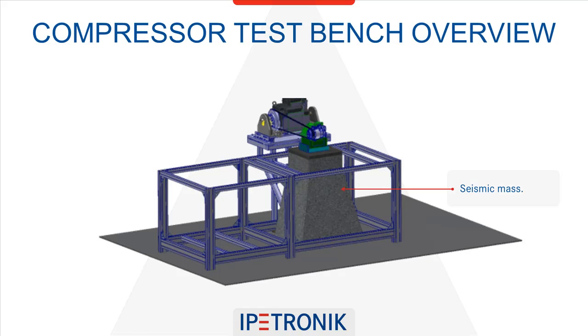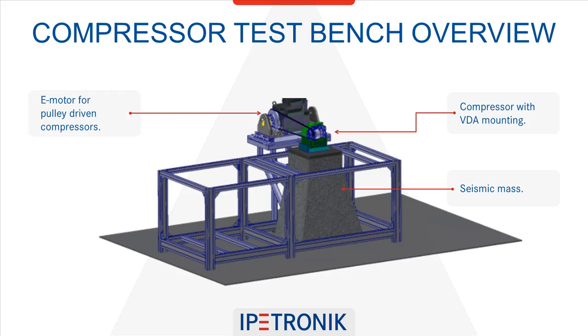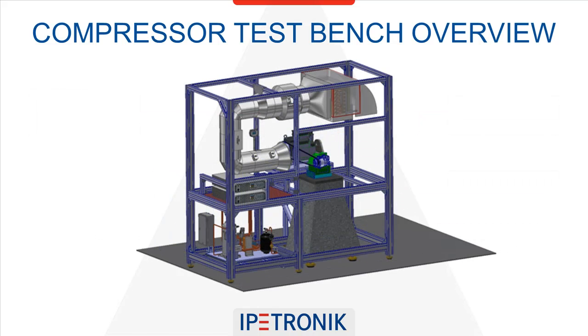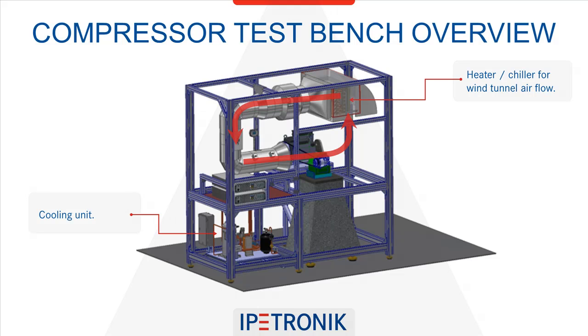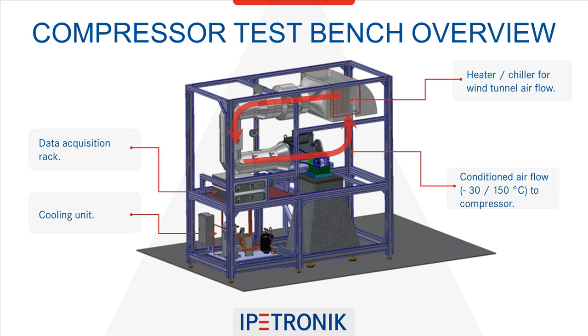The centerpiece is the seismic mass with the standard VDA mounting bracket for the compressor. Mechanically driven compressors have a pulley drive from a regulated electrical motor. In this view, you see the air conditioning unit. The wind tunnel provides conditioned and flow-regulated air to the compressor box to simulate different ambient temperature situations. The cooling unit is for the air conditioning and supplies cold airflow up to -30 degrees Celsius inside the wind tunnel. The data acquisition rack is equipped with ruggedized IPETRONIK measurement modules to measure data during the test.